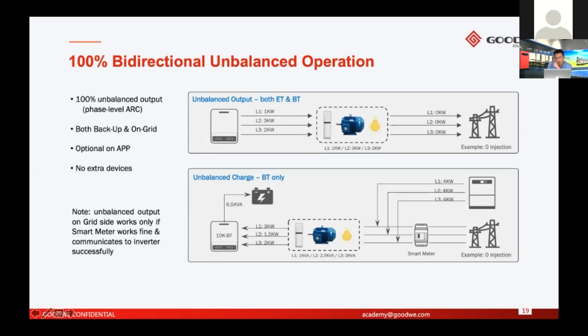So if the solar production cannot export to the grid, and on each phase you connect different loads, and the inverter cannot output unbalanced power, it means each phase has to output the same power. For example, if the first phase is a 1 kilowatt load, and the second phase is a 3 kilowatt load, and the inverter does not support unbalanced output ability, all three phases can output only 1 kilowatt. And for phase 2 and phase 3, the load power is higher than 1 kilowatt, so on these two phases, they have to buy from the grid. So this is a big waste of solar power, right? That's why unbalanced output is very important for places with zero export functions.